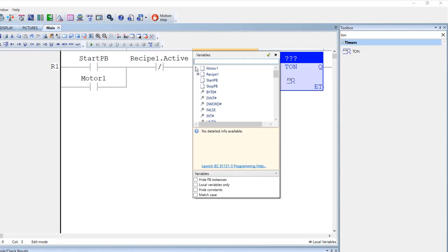Say, in order to prevent spurious signals, you want to make sure that someone who presses start really intends to press start, or someone who presses stop really intends to press stop. So you put in a debounce, which is normally done using a timer in the program.